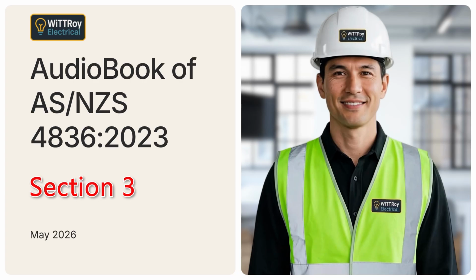Only competent persons may carry out fault-finding work on or near exposed energized conductors or live conductive parts. When fault-finding near live parts, controls must be used to prevent simultaneous contact with conductors at different voltages, or contact between a conductor and earth. Suitable PPE must be worn or used. The PPE must fit the person correctly and must be in good condition. Fault finding must be done from a stable work position.